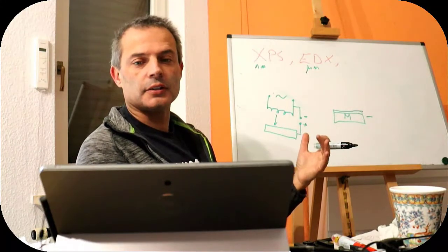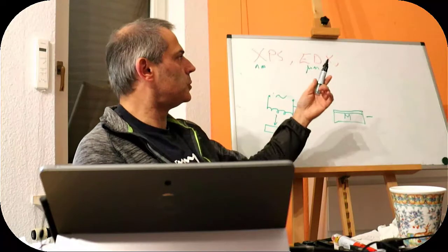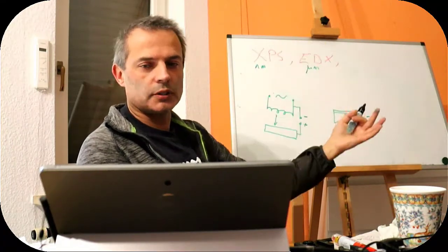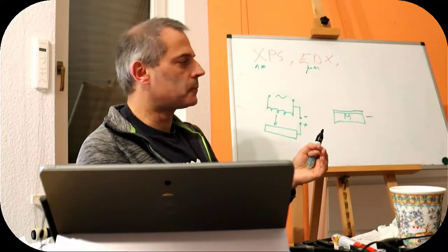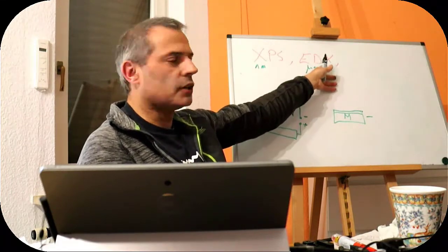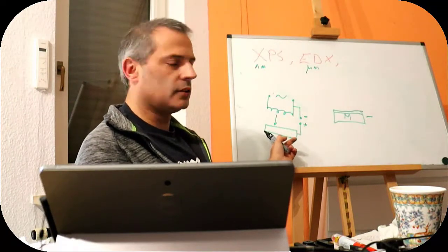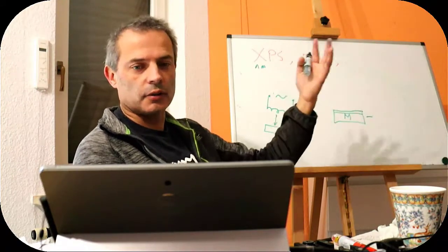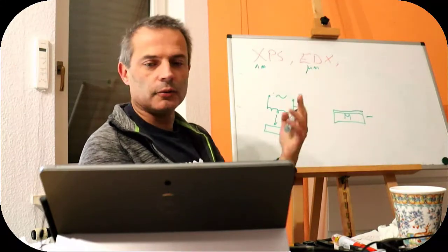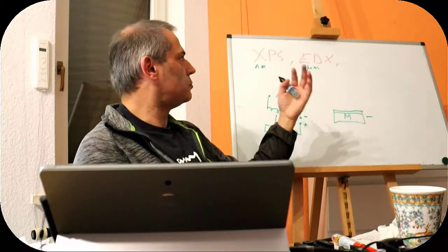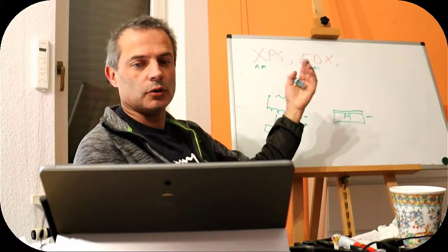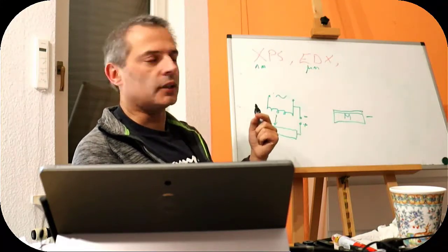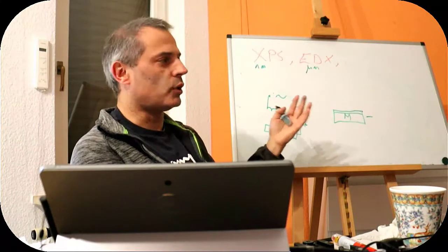The positive electrode has to be another metal because it is going to do something very similar to the EDX process to generate X-rays. So X-rays are going to be generated by electrons hitting the electrode and exciting electrons, and then other electrons falling back in, and that generates our X-rays. The problem is, well, the issue is that we generate lots of different X-rays, and there is another type of X-rays which are given a German name and there is no English name, Bremsstrahlung.